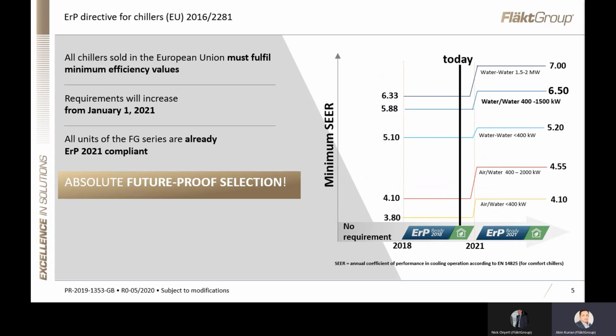So if you look at this graph, you can see the current SEER demand for an air-cooled chiller between 400 and 2000 kilowatts is 4.1, and today we are here. From January 2021, the requirement will be 4.55. Similarly, for a water-cooled chiller between 400 kilowatts and 1500 kilowatts, the current requirement is 5.88. And from January 2021, the requirement will be 6.5.